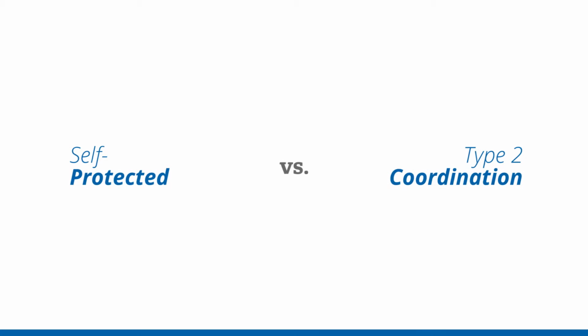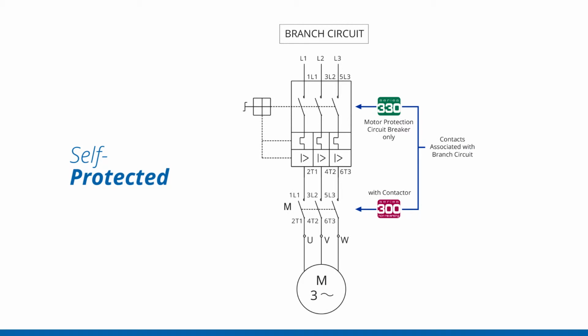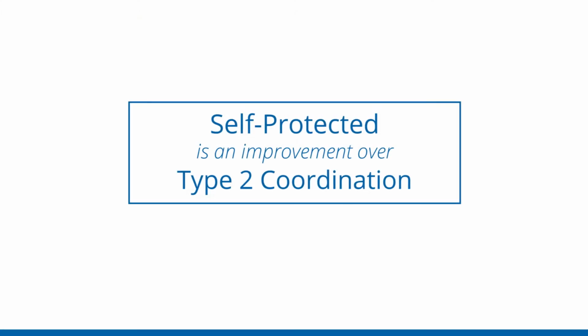Comparing this against Type 2 coordination, self-protected is associated with the contacts that serve as the branch circuit protection. It cannot weld, and it has to be able to operate immediately after the magnetic trip-out test or the fault. A Type 2 coordination indicates that the controller shall not result in danger to persons or the installation. After the short circuit, the controller may be capable of further use, however the contacts may weld, and there may be an appropriate level of maintenance allowed prior to them operating. So self-protected is an improvement or an increase over Type 2 coordination.